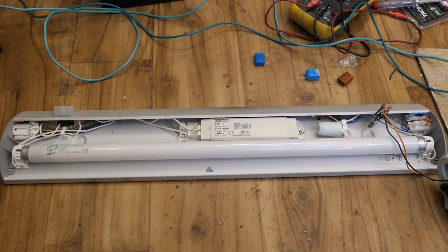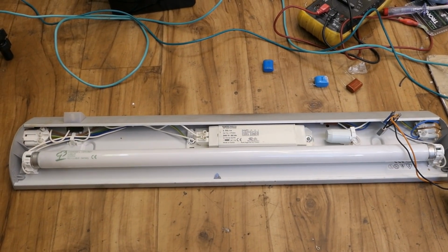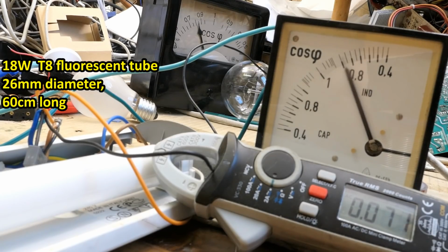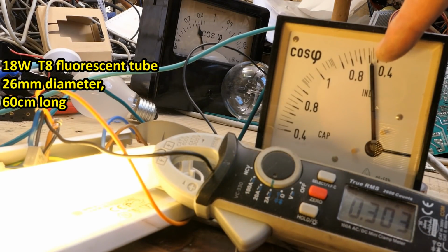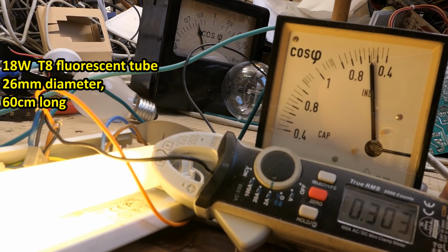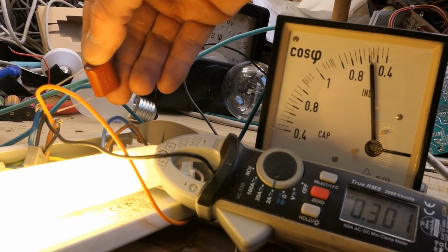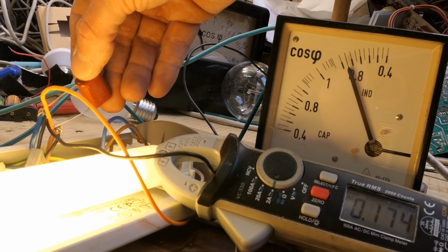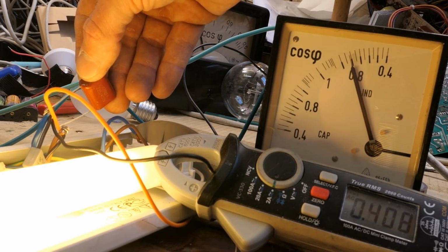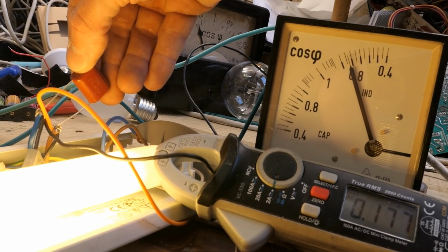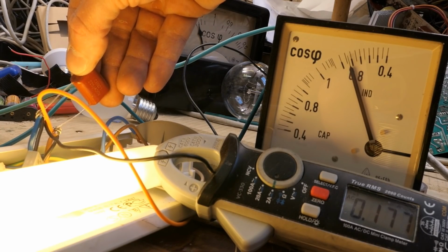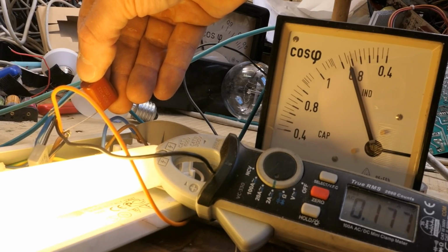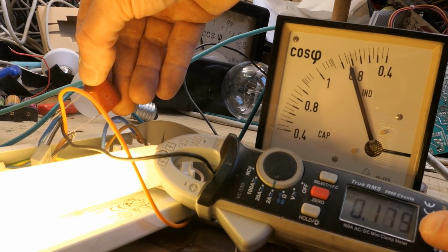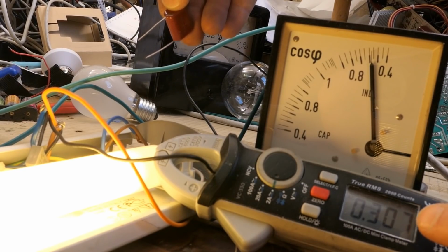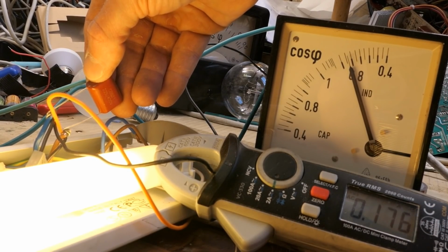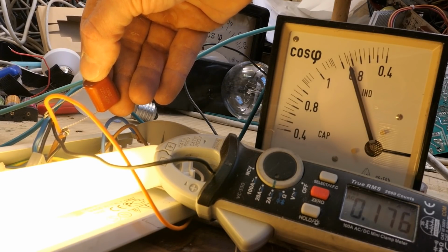And now, of course, a fluorescent fixture cannot be missing. And it indicates on the inductive side, and it draws over 300 milliamps. And if I stick a parallel capacitor to it, the power factor goes closer to 1, but not entirely so. For full compensation, this actually requires even more capacitance. But you can see that with the capacitor, it actually draws significantly less current. Without the capacitor about 300 milliamps, with the capacitor about 170 milliamps.